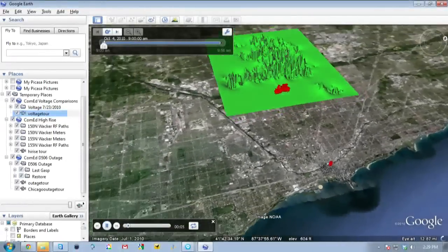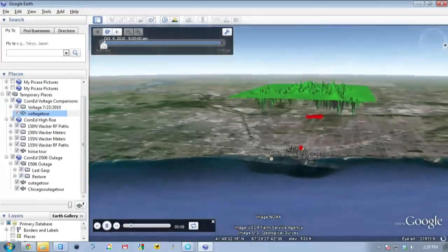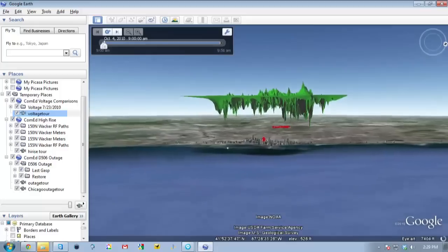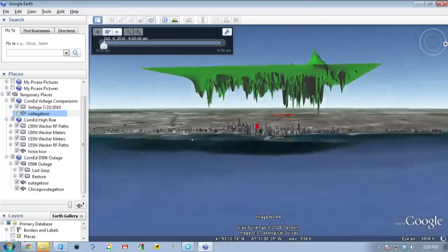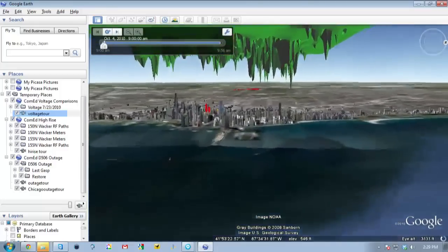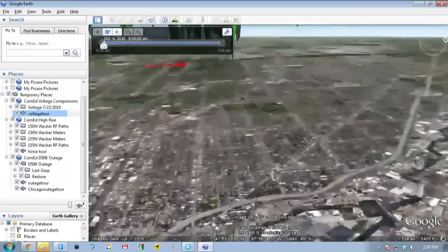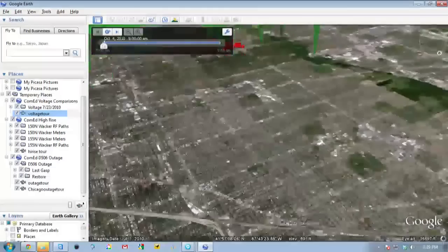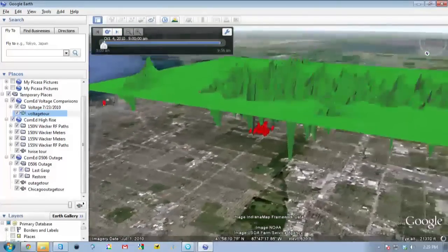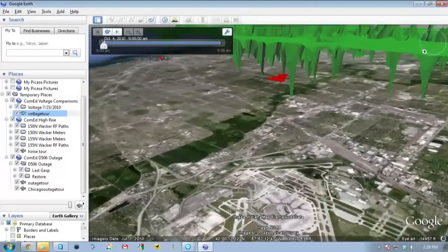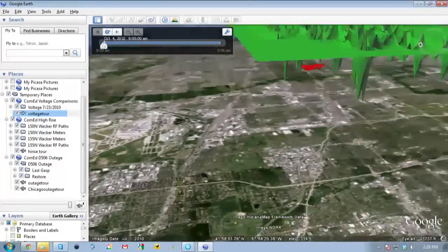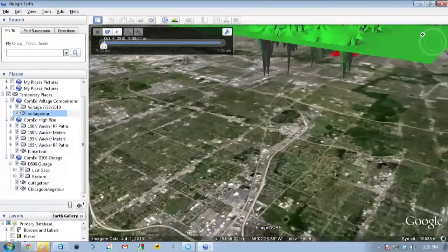Once you have these meters in place, the utility can now be proactive as opposed to reactive. They can look at things like voltage on a hot summer's day. Here we have a mesh of 130,000 meters over the city of Chicago on one of the hottest days of the year. The utility can now look at low spots in the grid caused by excessive use of air conditioners and be proactive — go out and fix the infrastructure before it causes problems for customers. This will also help when electric vehicles are more prominent, because electric vehicles will be adding unexpected loads over time.